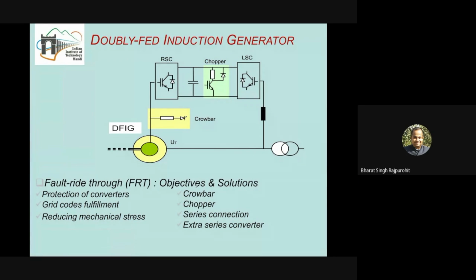But what about the reactive power? The reactive power in this case can be fed to the grid by using this line side converter. This line side converter can act as a static compensator, and it will be able to generate reactive power and feed it into the grid by using this DC link capacitor. During normal time, the reactive power is pushed by the rotor side converter into the rotor of the DFIG, which is then able to utilize it for magnetization of the air gap and the other windings by using this DC link. So the reactive power requirement of this DFIG can be met by the rotor side converter.